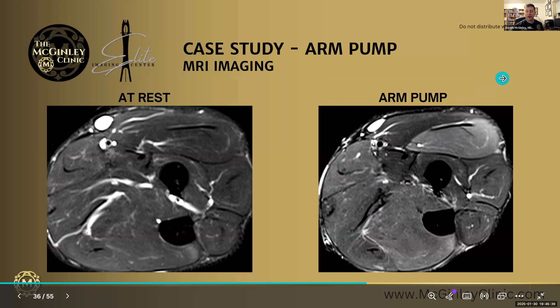Traditional compartment pressure testing using needle compartment measures, I would encourage you to stop doing that. If you actually look at the data on that, most people, 95%, don't even follow the protocol correctly. And I did a test on this. I got a meat sample. I put one of those pressure devices, one of the Stryker pressure devices in it. And depending on ever so slightly, I'd push on the syringe. I can get numbers from 5, so normal, all the way up to 100 in the exact same position in the meat sample. So it's very subjective, and it's very subjective to bias within those studies. So the MRI protocol is non-biased. You scan them at rest, do the same protocol, and scan them afterwards. You can visually see the swelling within the muscle structures. This works for lower extremity as well as upper extremity.